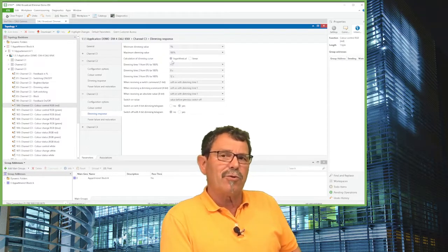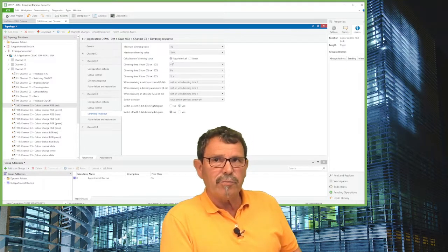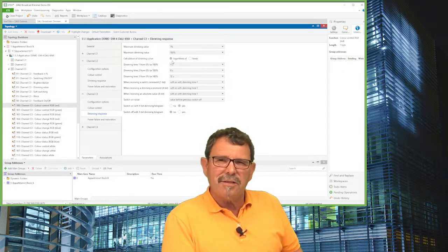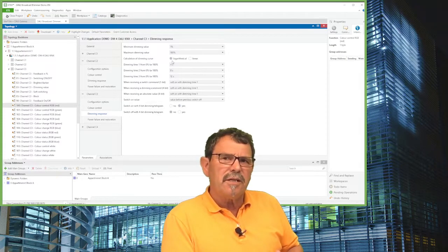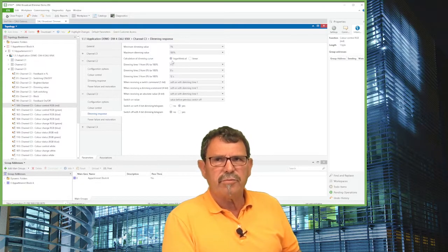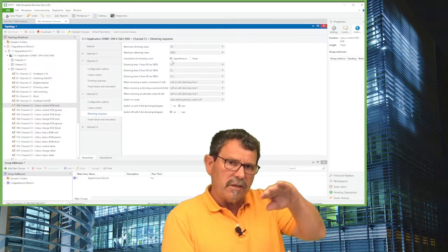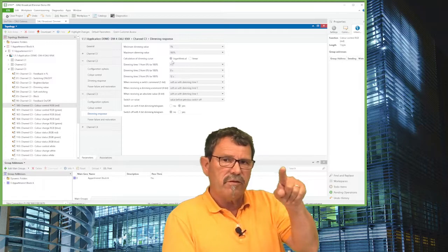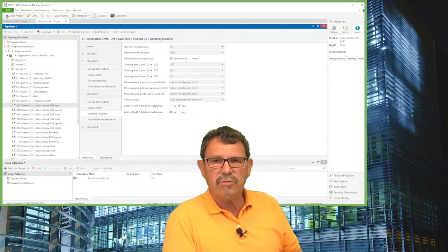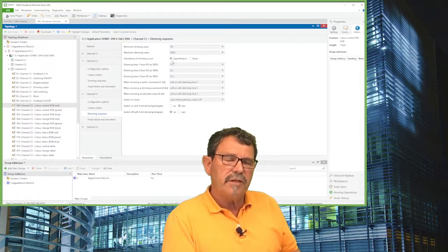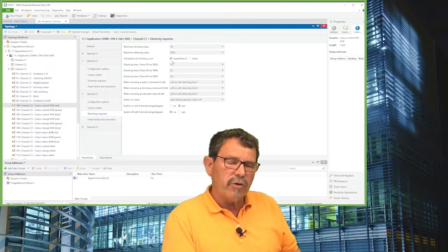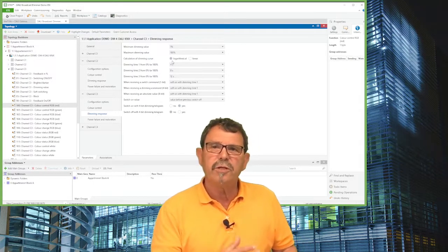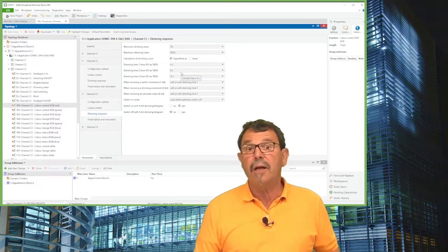There's also the dimming curve setting: logarithmic or linear. The human eye perceives light in a logarithmic way, so a logarithmic curve is more fitting to natural human light reception. With a linear curve, if you input 40 you get 40 output, and 60 gives 60 — it's perfectly proportional. Logarithmic curves have different rate-of-change characteristics that better match how we perceive brightness. Note that the light itself also needs to support this ability.